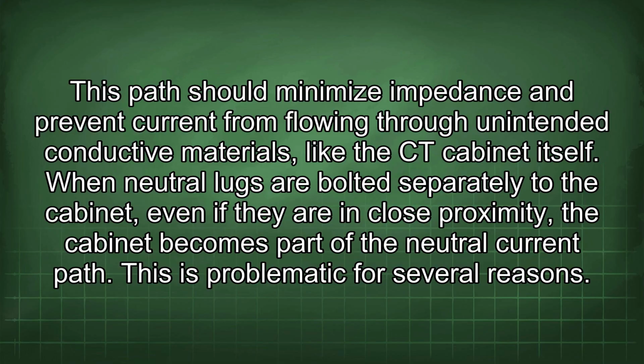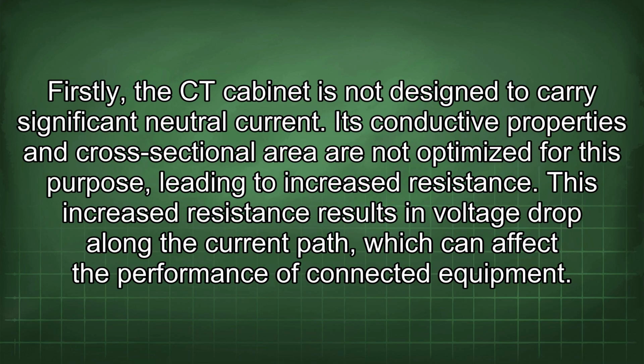When neutral lugs are bolted separately to the cabinet, even if they are in close proximity, the cabinet becomes part of the neutral current path. This is problematic for several reasons. Firstly, the CT cabinet is not designed to carry significant neutral current. Its conductive properties and cross-sectional area are not optimized for this purpose, leading to increased resistance. This increased resistance results in voltage drop along the current path, which can affect the performance of connected equipment.